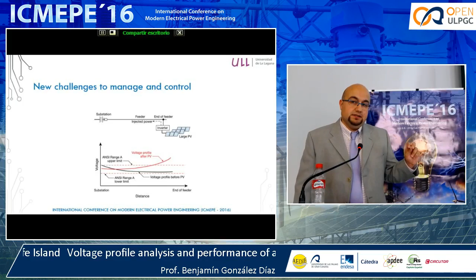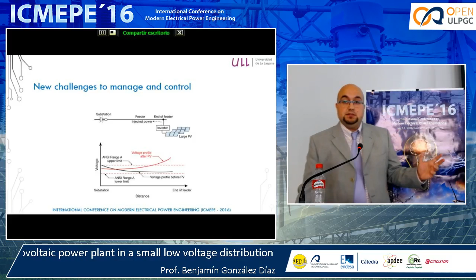What problem are we expecting? Actually, in the radial configuration, if we look at the black line, we can see the voltage profile from the substation to the end of the feeder. As expected, due to the resistivity of the cable, the voltage decreases.